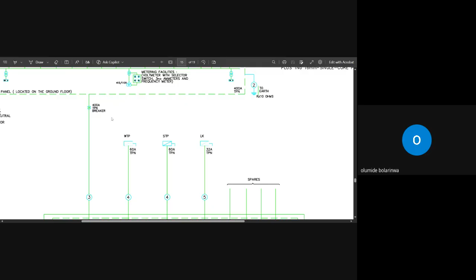Now you can see there's a reason why we have the 400 amps TPN breaker. You can't have an outgoing of 400 and your breaker be 200. It's not possible because the outgoings must be the same rating as your breaker.